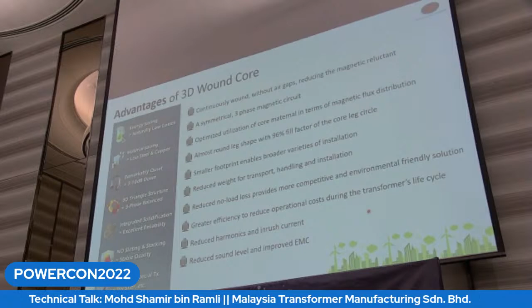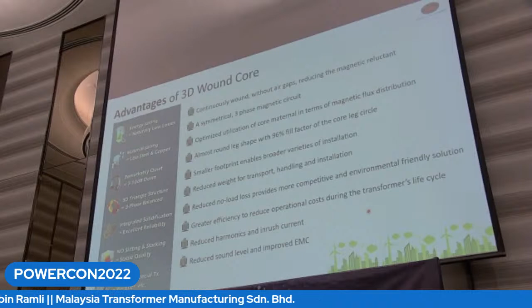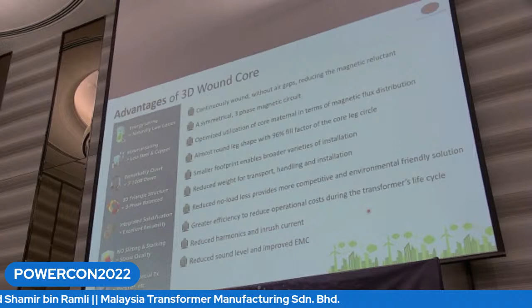So in summary, the advantage of the 3D wound core is energy saving based on our study at the moment, with naturally low losses. It also gives material saving in terms of steel and copper, and it is relatively quiet, with a 7 to 10 decibel reduction from our conventional transformers. With the 3D triangle structure, the three-phase magnetic is more balanced. With integrated solidification and vacuum impregnation, it gives excellent reliability. We also noticed that the transformer with this technology can be used for other special applications as well.